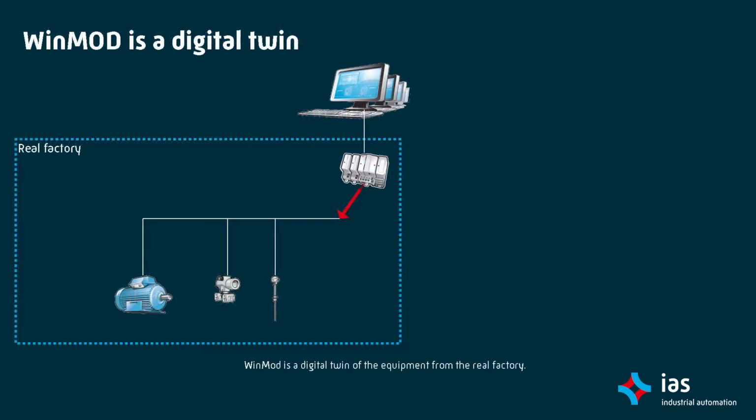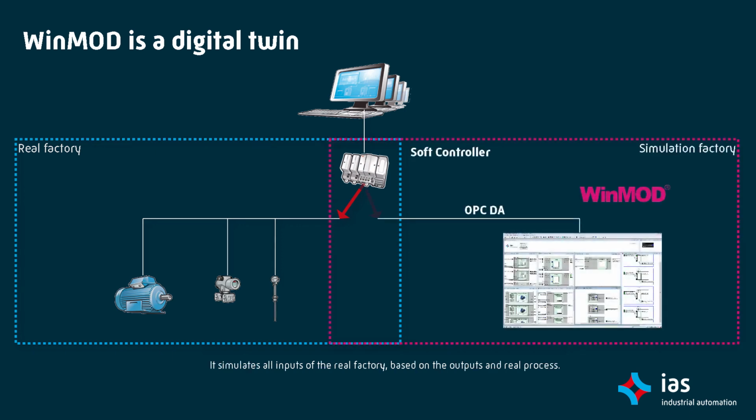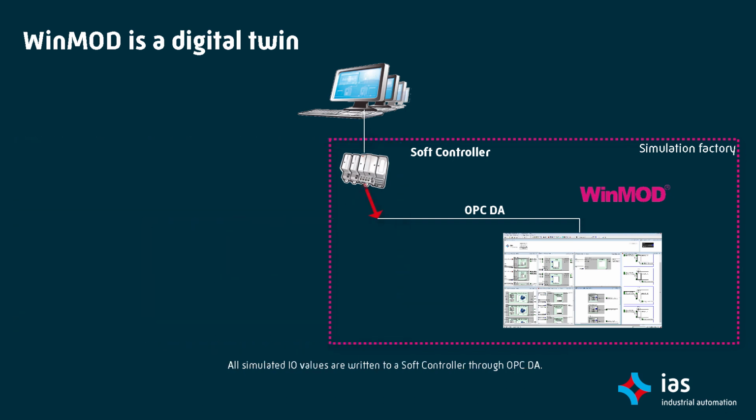WinMOD is a digital twin of the equipment from the real factory. It simulates all inputs of the real factory based on the outputs and real process. All simulated I/O values are written to a soft controller through OPC-DA.